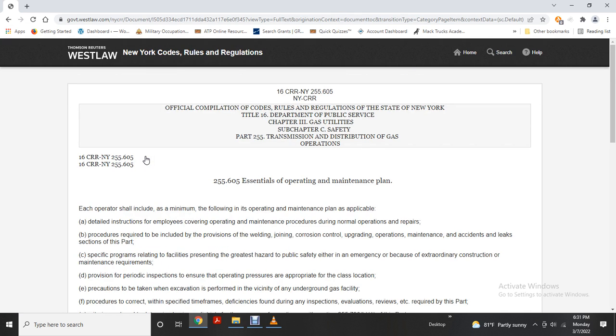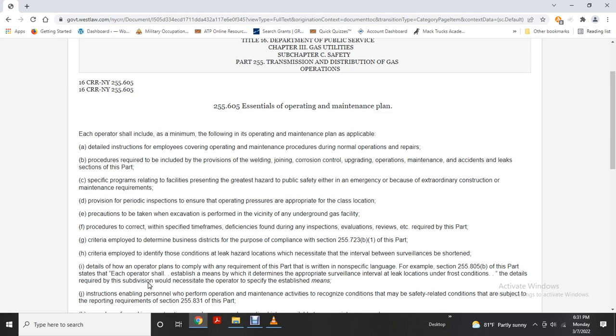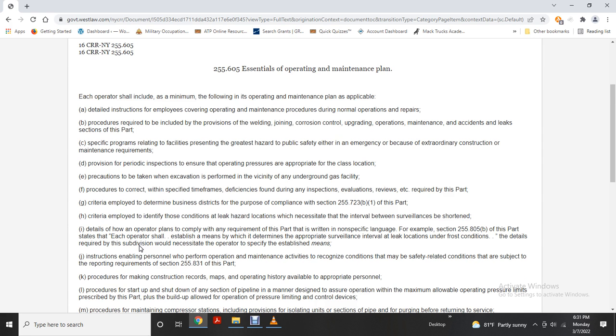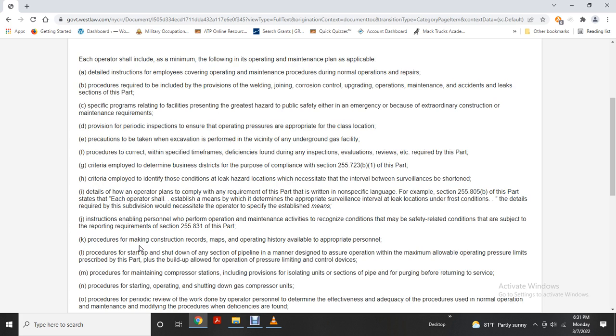Essentials of the Operating and Maintenance Plan. Each operator shall include, at a minimum, the following in its operating and maintenance plan: detailed instructions for employees covering operating and maintenance procedures during normal operations and repairs; procedures required to comply with the provisions on welding, joining, corrosion control, upgrading, and operation and maintenance of accidents and leaks in sections of this part; specifically, programs relating to facilities presenting the greatest hazards to public safety, either in an emergency or because of extraordinary construction or maintenance requirements, including provisions for periodic inspection and ensuring the operating pressure is appropriate for the class location; precautions to be taken when excavation is performed in the vicinity of underground facilities; procedures to correct, within a specified time frame, deficiencies found in any inspection, evaluation, or review required by this part; and criteria employed to determine the business districts for the purpose of compliance with section 255.723B1 of this part.